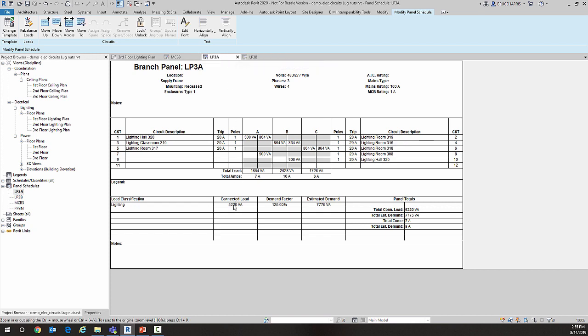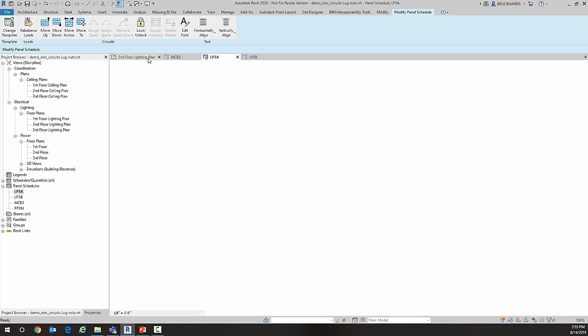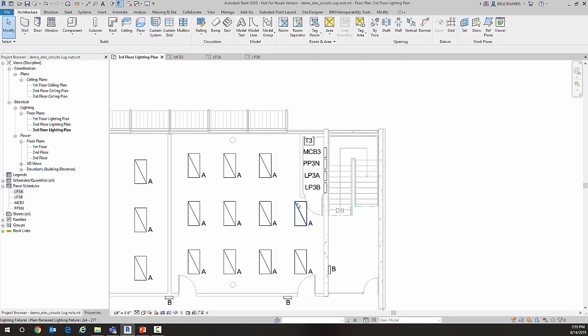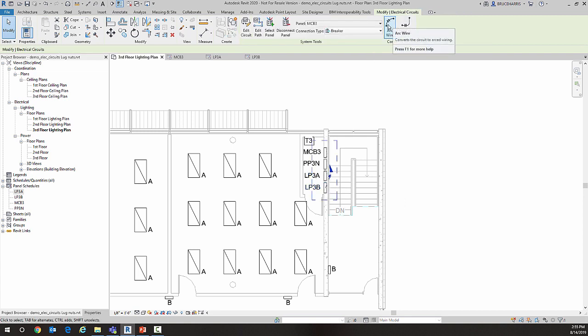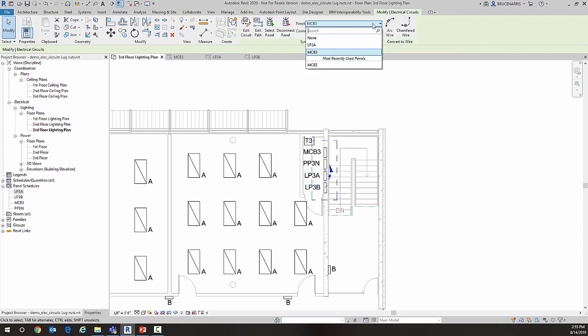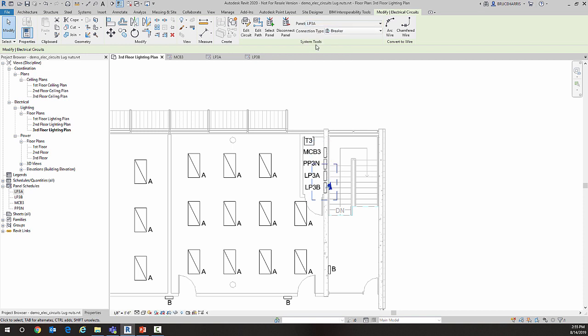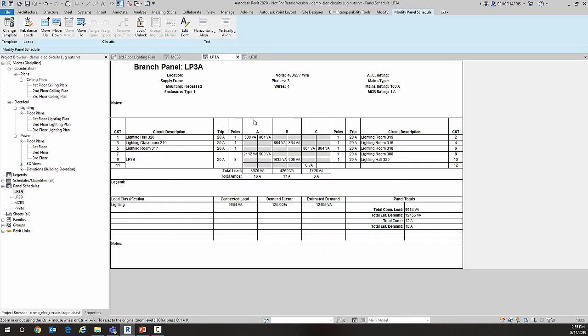Now I'm going to circuit LP3B through to LP3A, which currently has 6,220 watts. Just like creating a circuit earlier, I simply select the panel, go to Power, and choose the panel I'm going to connect it to—in this case, LP3A. When I do this, notice it puts a breaker here on LP3A, and I have the combined load of the two panels together.